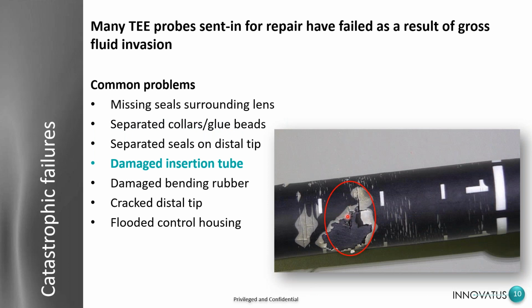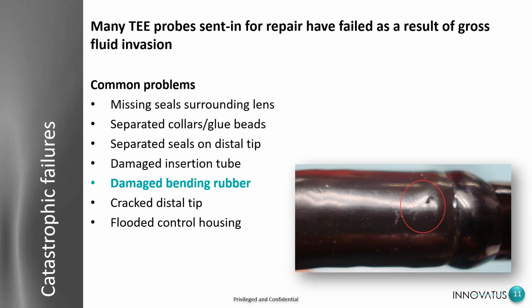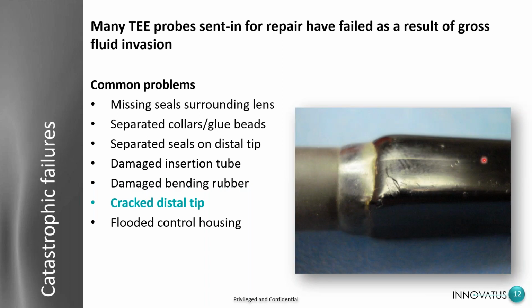Damaged insertion tube. Obviously, this is gross damage on the insertion tube. Damaged bending rubber. We have a nice tooth mark here on our bending rubber. And it doesn't take much. Just a tiny pinhole will allow fluid to get inside a probe. And the cracked distal tip. This is the tip at the very end of the probe that contains the array and possibly a motor control.